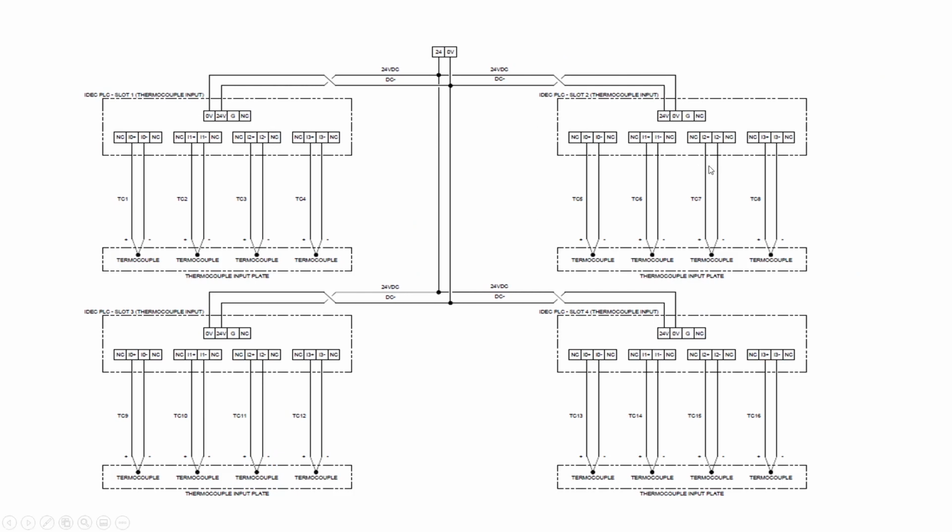Here we're not looking at a digital input or an analog input. We're looking at something a little bit different. These are thermocouples. So again, this is a different type of signal or input or output. Here you see we have power that's being supplied to, looks like a PLC card. In this case, these cards require power in order to do the monitoring that they need to. And then you can see there's several sets of terminals for one signal. Depending on the manufacturer of the PLC or the card that you're using, you need to wire to different terminals. So in this case, you've got 4 different terminals you can wire to depending on the specific application.